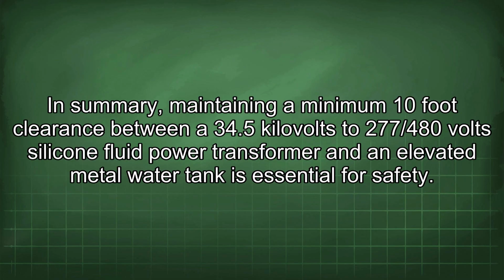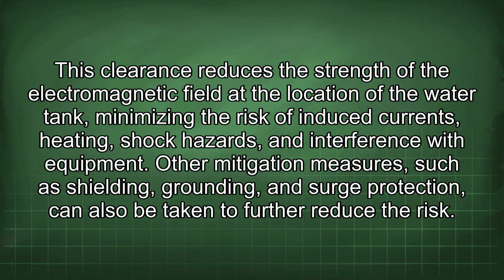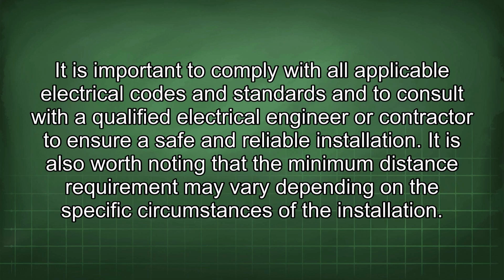In summary, maintaining a minimum 10-foot clearance between a 34.5 kV to 277/480 volt silicone fluid power transformer and an elevated metal water tank is essential for safety. This clearance reduces the strength of the electromagnetic field at the location of the water tank, minimizing the risk of induced currents, heating, shock hazards, and interference with equipment. Other mitigation measures such as shielding, grounding, and surge protection can also be taken to further reduce the risk. It is important to comply with all applicable electrical codes and standards and to consult with a qualified electrical engineer or contractor to ensure a safe and reliable installation.